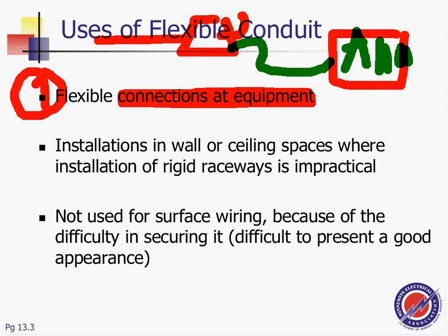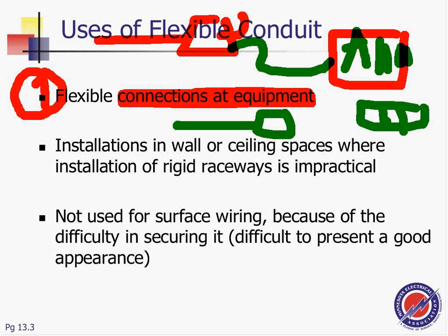One application. The other application, guys, is I have my lighting fixture here, and I have a J-box, right? I have my EMT coming from it. And what do I do? I bring my flex and I flex it all the way to my lighting fixture. So that's a very common application, tying to equipment, machines, units. So that's the major use, basically, of flex. Another application of flex is not as common as connection to equipment.